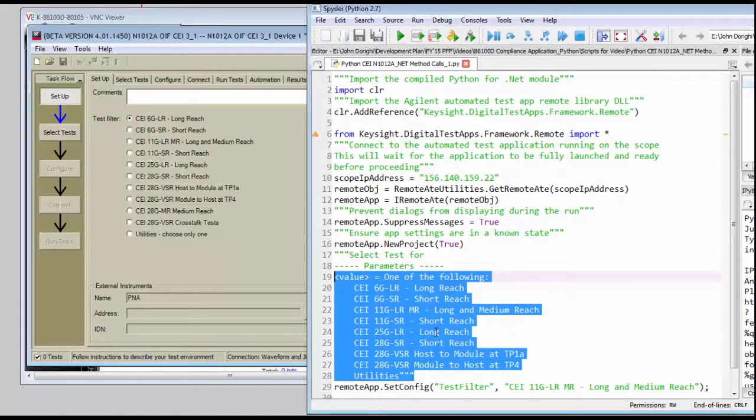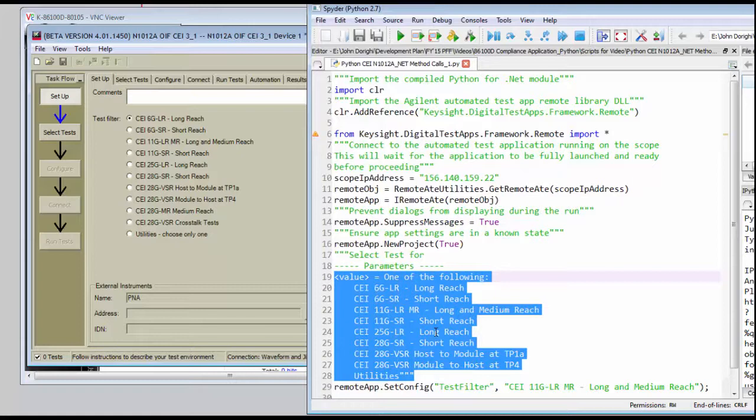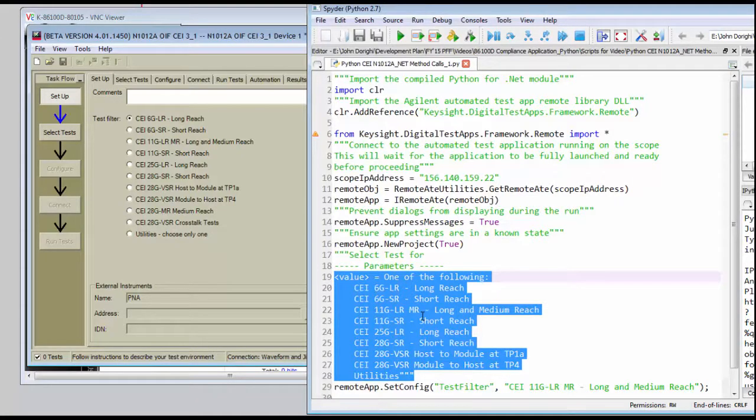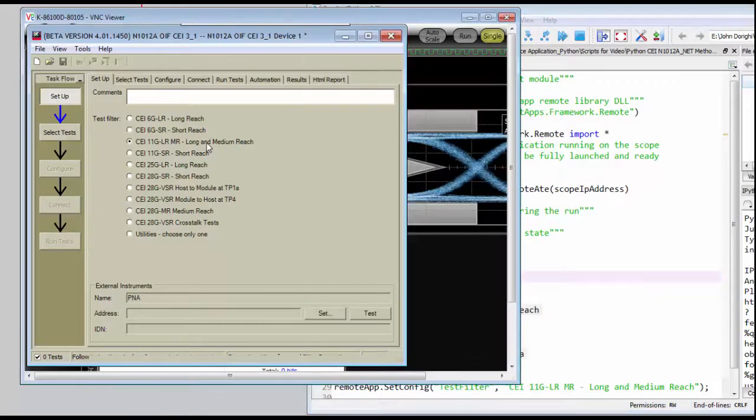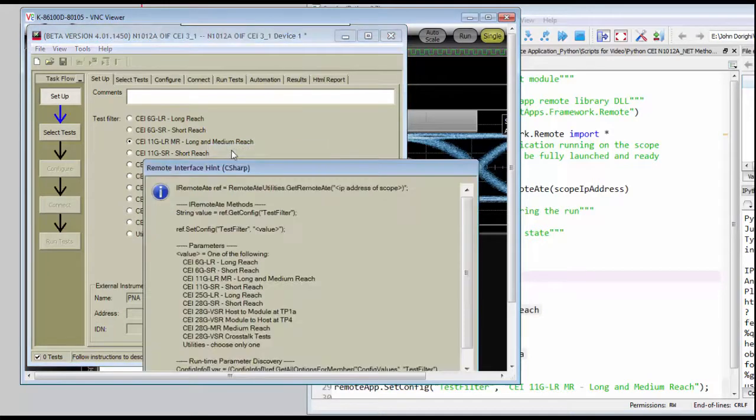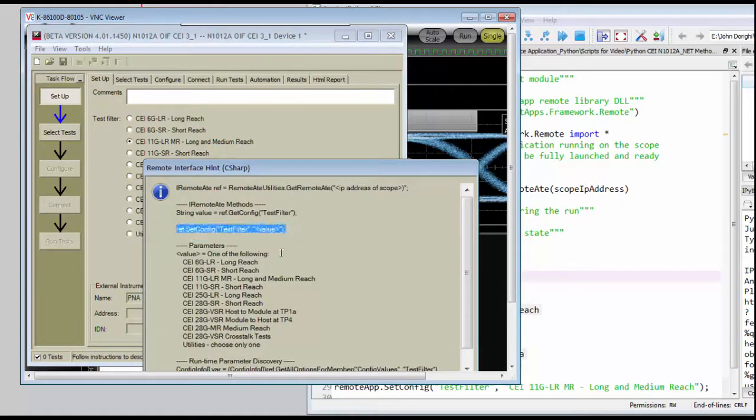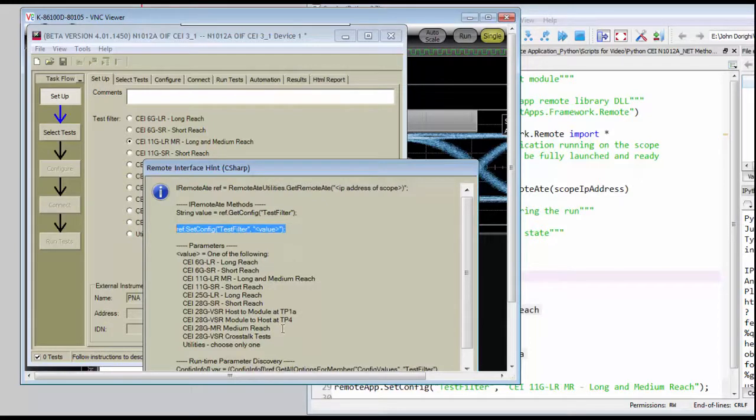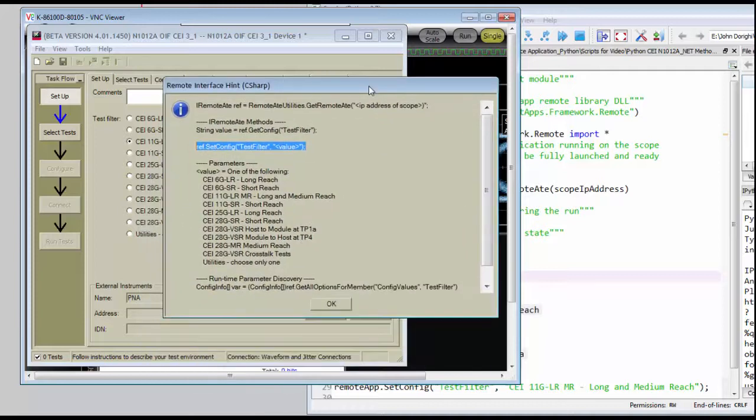A real important point to eliminate a lot of the guesswork in setting up the tests is to take advantage of the hints that are available inside the compliance app. So we've enabled the hints, and we can go to any of the various test filters, right-click on it, and ask to see the remote interface hint. And this shows us not only the method that we'll need to set up and select that filter, but also what the range of parameters are in order to do that, to select a specific test.